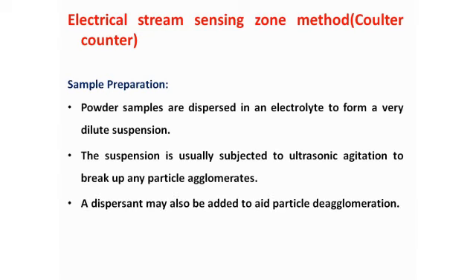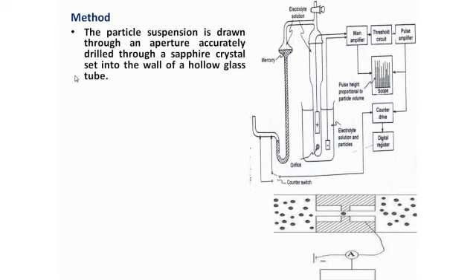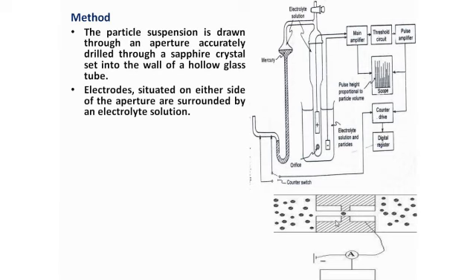This is the diagram of the instrument. The particle suspension is drawn through a small orifice or aperture. The electrodes are situated on either side of the aperture. They are surrounded by the electrolyte solution.